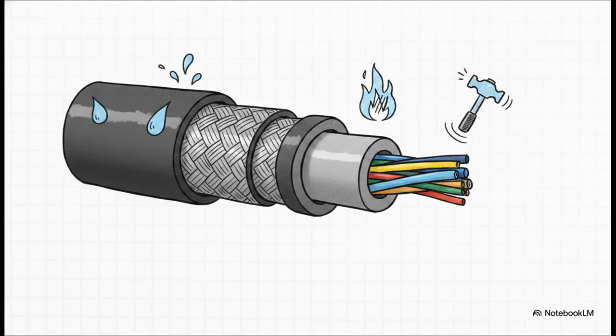Okay, let's strip back a compliant Zone 0 or Zone 1 cable to really see its anatomy. You definitely can't just run standard industrial wire here. The rules are strict. First off, you need an outer, non-metallic, impervious sheath to fight off chemicals and moisture. It also has to have a flame-retardant material marking. Beneath that jacket, you must have continuous metallic armor or braiding. And of course, there are minimum conductor sizes applied.